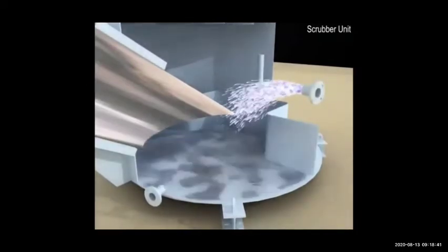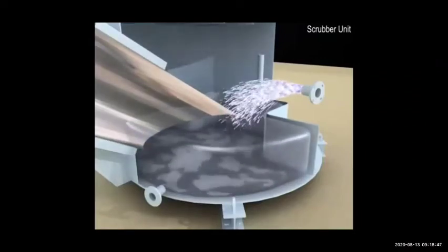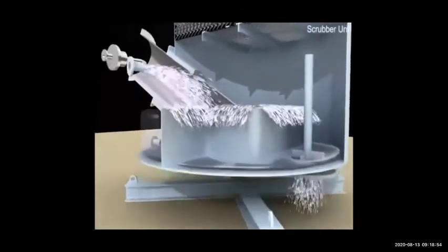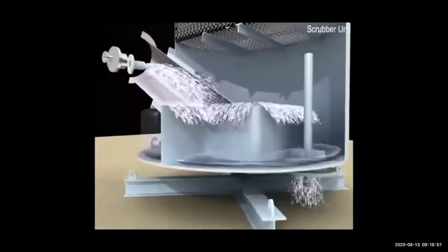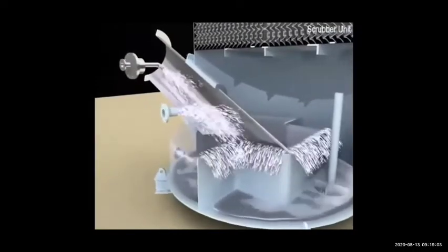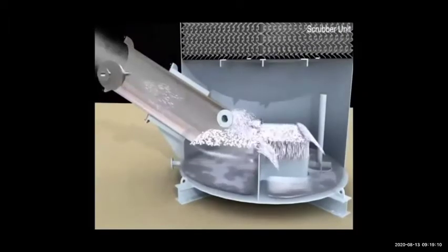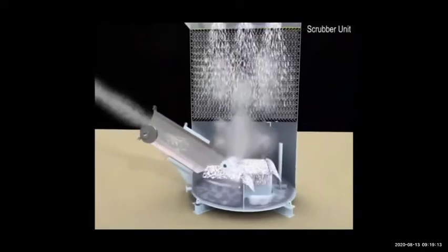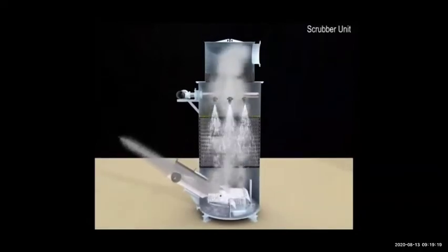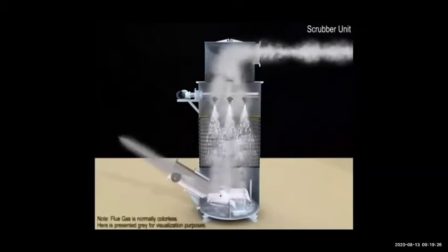The water is filled at the bottom and gas is passing through the water because it is hot and we want it to cool down. Gas is lighter so it will come up through the water. This part of the scrubber will always be filled with water. You can see the gas entering, passing through the water and baffle stones, getting sprinkled. All impurities come out and the gas passes out of the scrubber through the demister pad. All moisture is absorbed here.